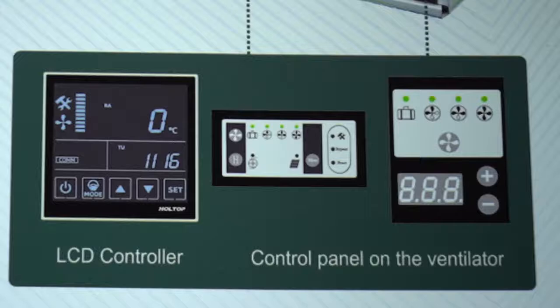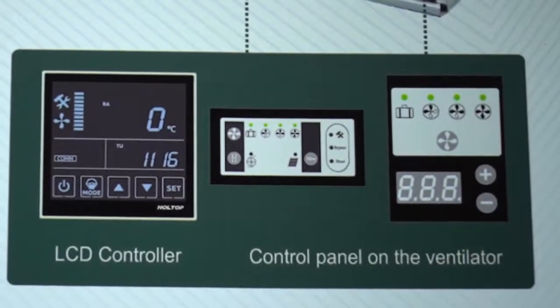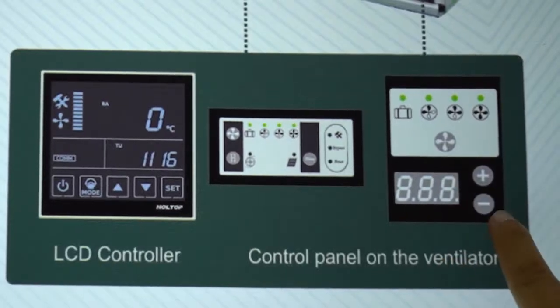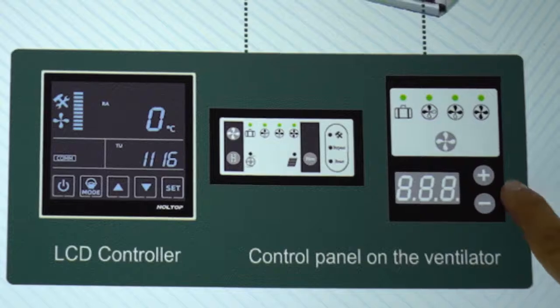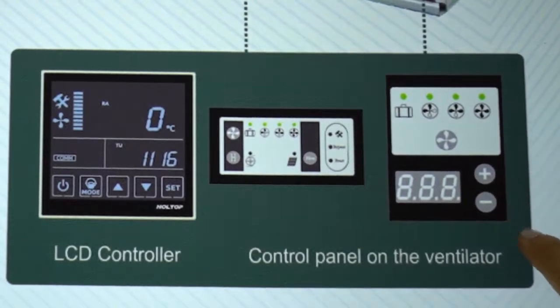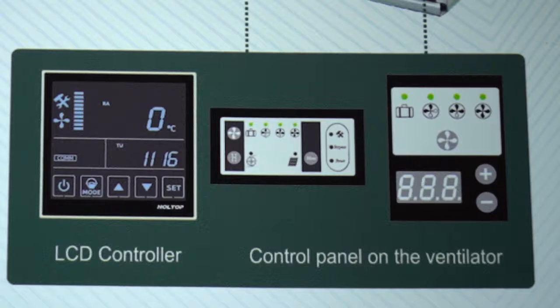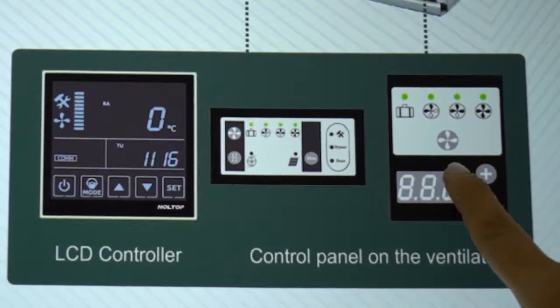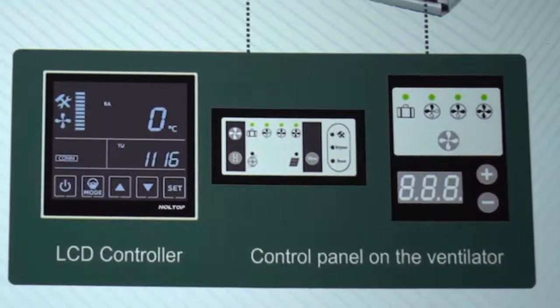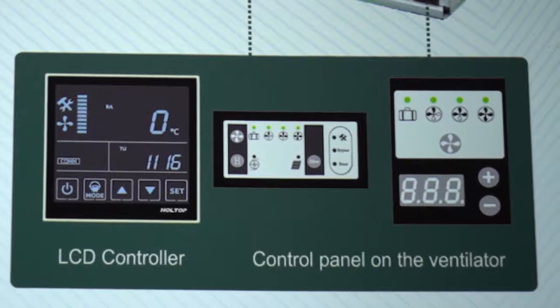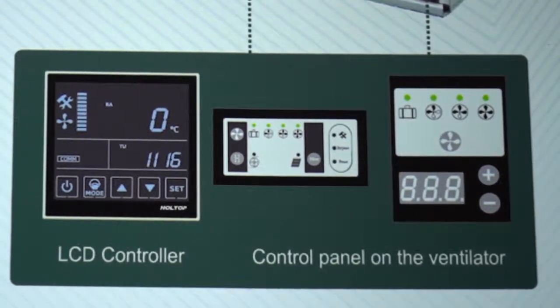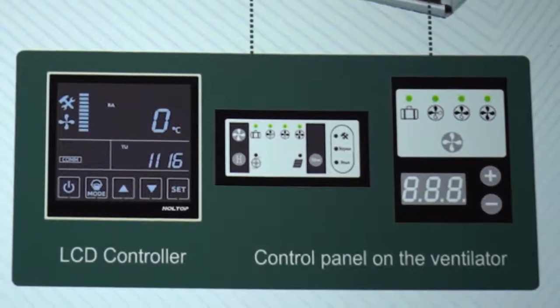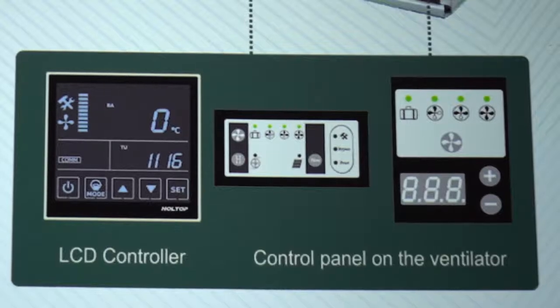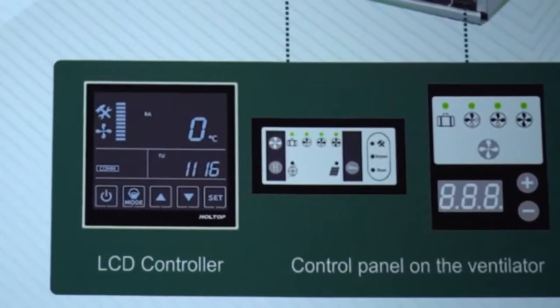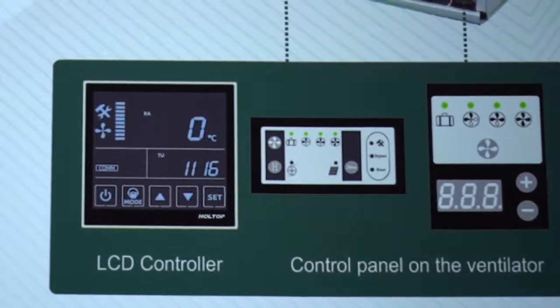Now let me show you more details about the sub-control panel at the right corner of the machine. There are 3 buttons on this panel. This one is the fan speed control button, and we adjust the fan speed by the up and down buttons. If we press this button one time, then we adjust the fan speed. This is simple. And after 15 seconds, the setting will be saved. Well, if we press this button for 6 seconds, then we can adjust the fan speed for the supply air and the exhaust air separately. So by this means, we could achieve indoor positive air, negative air, or balanced air based on the specific requirements.